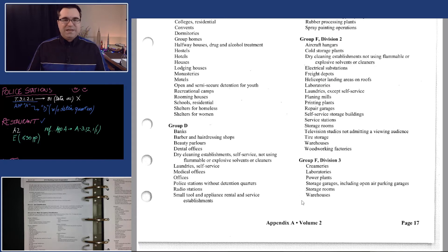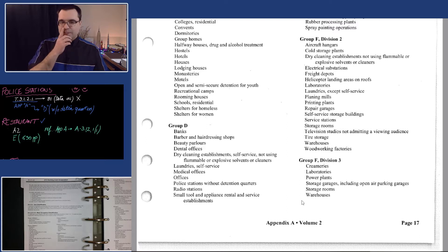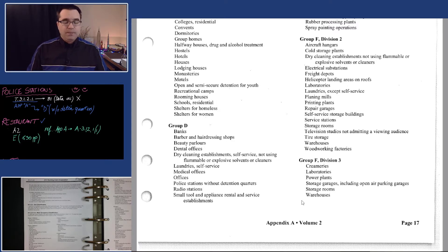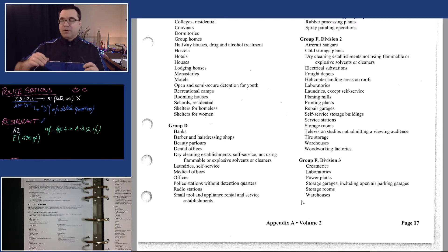F3? No. So it looks like we either have A2 or E to pick from, and the choice between the two comes down to the occupant load — how many people are in that restaurant. This was a tricky example I purposely picked to make a point. Had we just used Table 3.1.2.1, we might have found one of these occupancies but not likely both. By going through Appendix A first, we're able to look at all possibilities from A1 to F3.